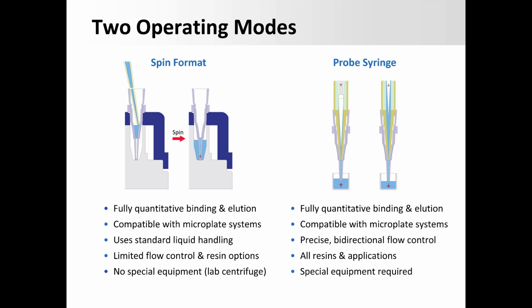The second mode is a way of getting exquisite control over the flow rate, what we call our probe syringe technology. And here we have the same features of fully quantitative binding and elution, and compatibility with microplates. But now we've coupled the cartridge to a syringe pump so that we basically can get perfectly precise bidirectional flow control. And this allows us to run a much broader range of media and applications, but it does require special automation equipment that incorporates this probe syringe technology.